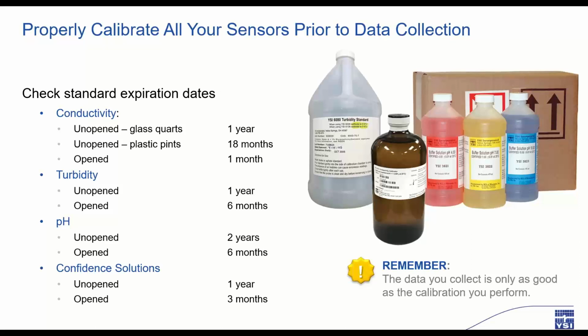YSI and most people's SOPs do not recommend or allow the use of expired standards. It is impossible to tell how they might adversely impact the calibration and thus lead to the collection of faulty data. Therefore, we do not recommend it. Please note that the expiration guidelines listed on the screen are for YSI manufactured standards. If you're using standards from another manufacturer, which is okay, be sure to ask their guidance on that particular product.